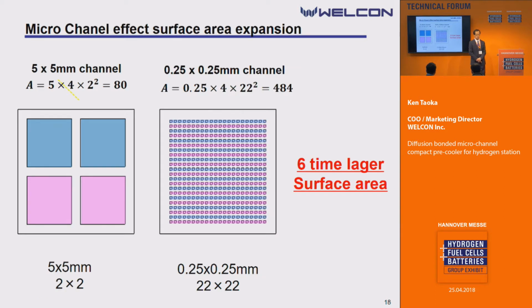Why are microchannels better? Because if you go into smaller size channels, you can gain a large surface area inside a small box. So smaller is better, basically. But at the same time, if you go too small, you're going to work against pressure loss. So you have to design and balance for what kind of gas or liquid you are going to use.